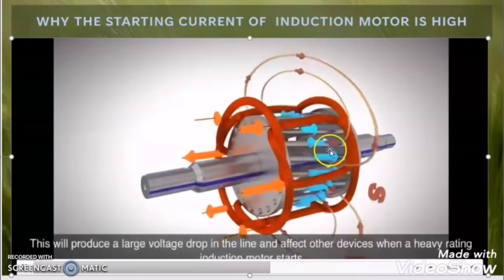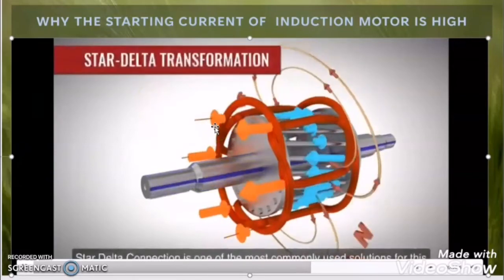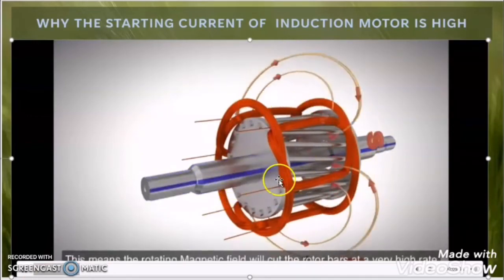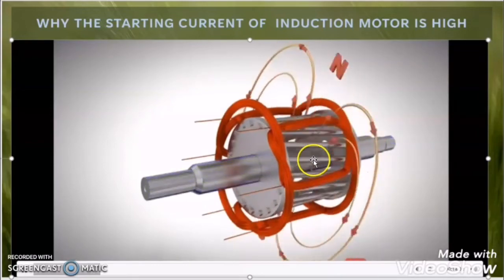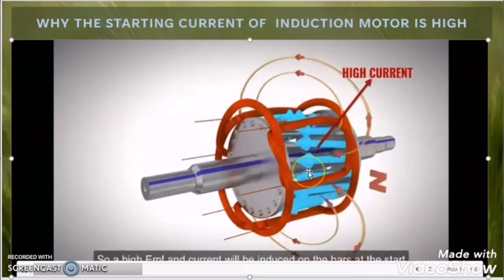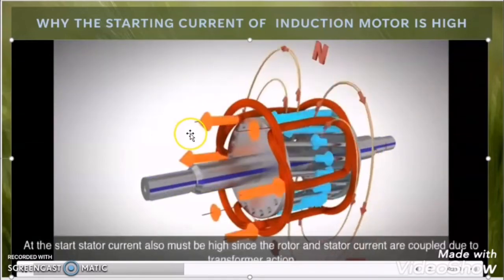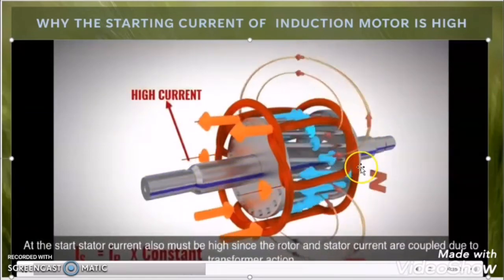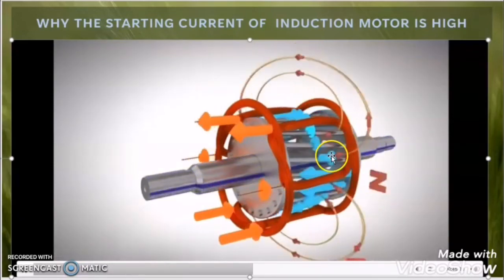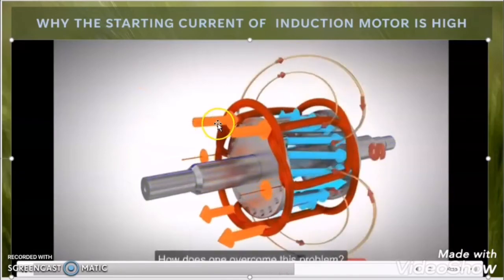But once the rotor starts rotating, the magnetic flux linkage with the rotor bar will become normal and there will be normal induced EMF and normal induced current in the rotor. So during running condition, the motor will only take rated current. We can conclude here that at the time of starting, the rotor is in the standstill position and the rotating magnetic field is cutting the rotor bar at maximum, so there is maximum induced EMF and induced current in the rotor bar. As the rotor and stator are coupled with transformer action, due to the high induced EMF at the time of starting, the stator winding also takes high inrush current. But once the rotor starts rotating, the flux linkage becomes normal, so the stator winding takes only the rated current during running.